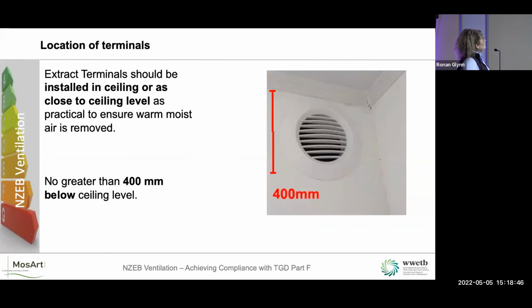So extract terminals should be installed in a ceiling or as close to a ceiling level as possible to ensure that warm moist air is removed. And that makes logical sense, doesn't it? Because the warm air rises. But if you have a vaulted ceiling and you put your extract right up in the very top of that, it's very difficult for somebody to commission it and to validate it. So that's where it should be. It should be up no more than 400 mil from the ceiling level.